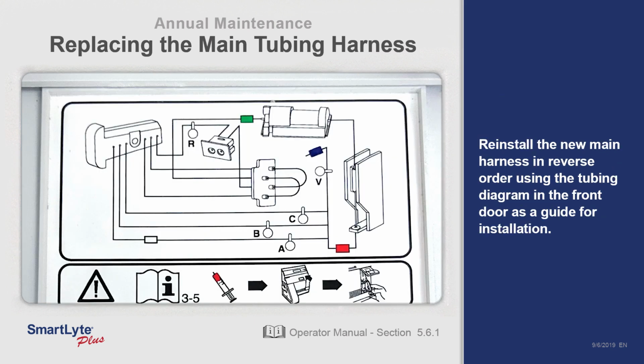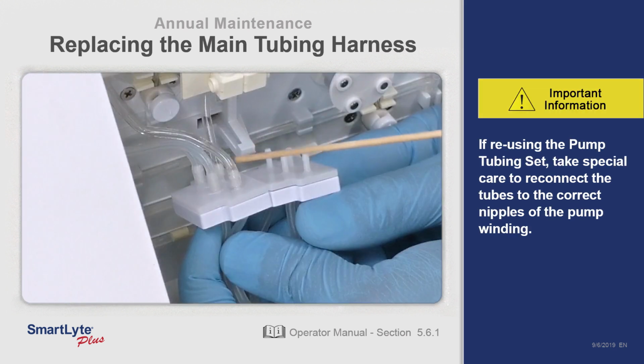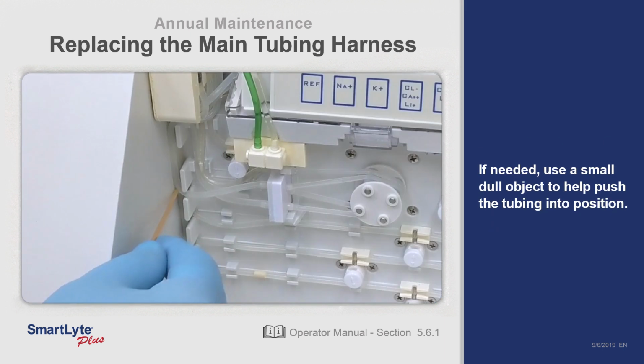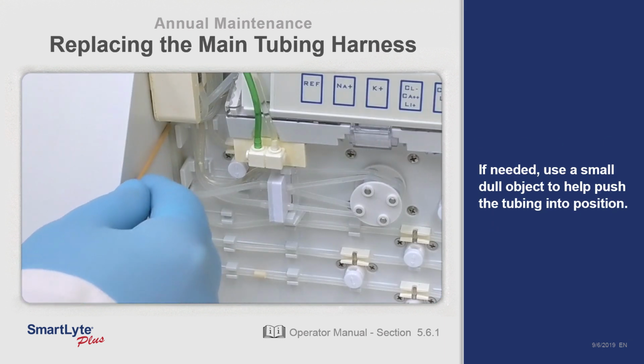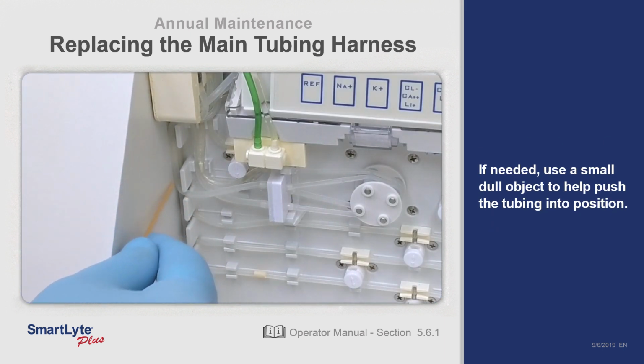Reinstall the new tubing harness in reverse order using the tubing diagram in the front door as a guide for installation. If reusing the pump tubing set, take special care to reconnect the tubes to the correct nipples of the pump winding plate. If needed, use a small dull object to help push the tubing into position.